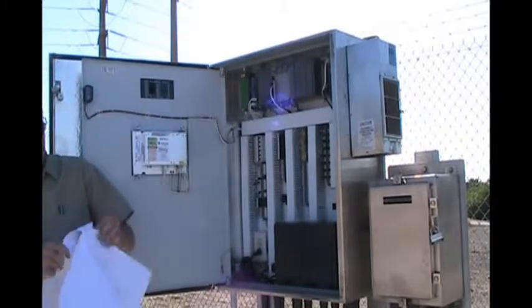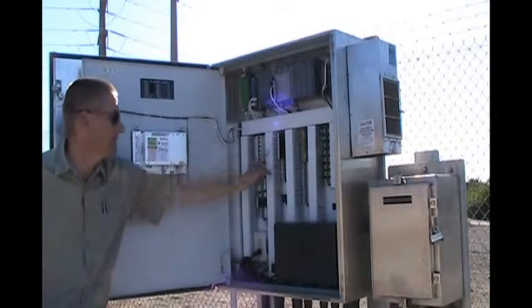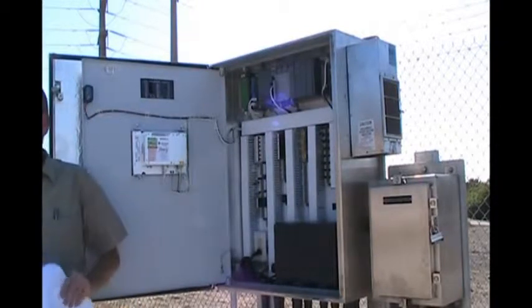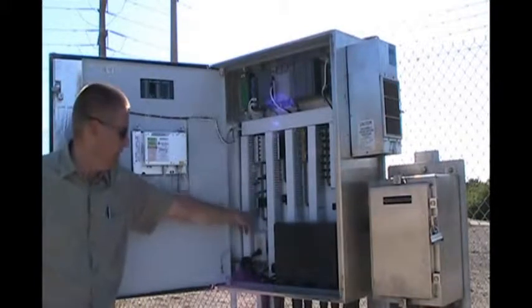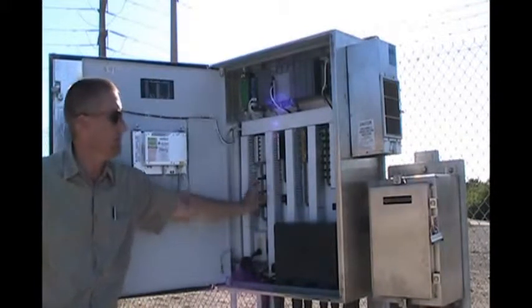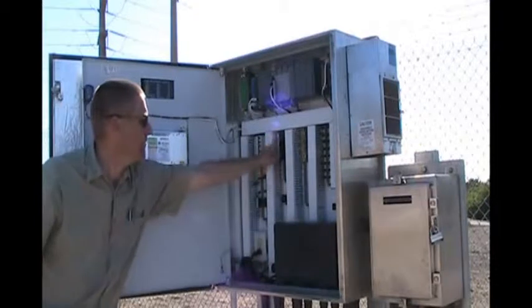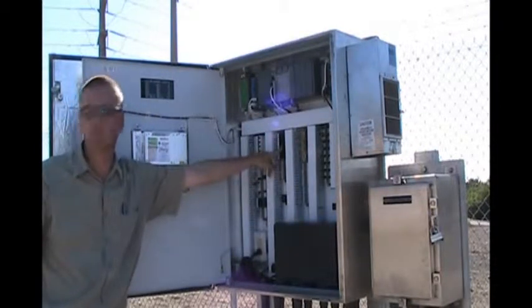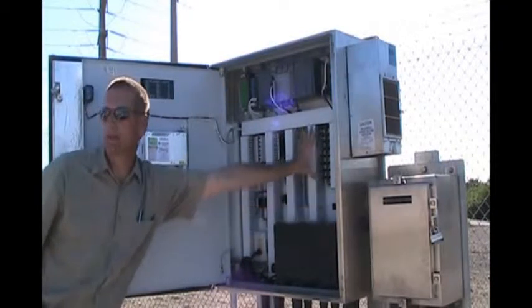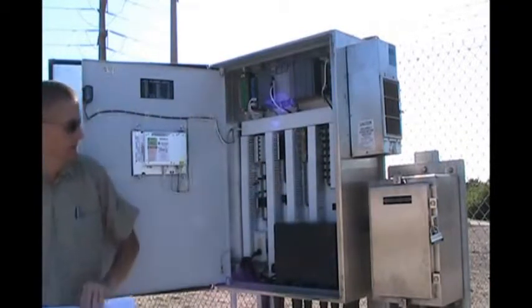And then we go into the 24, it'll all be fusing. And it's all laid out per digital I/O or analog I/O, the fusing will be close. So all digital, this would be digital fusing, more digital fusing. Each individual channel is fused. And then the analog is fused in the analog section of the terminal blocks.